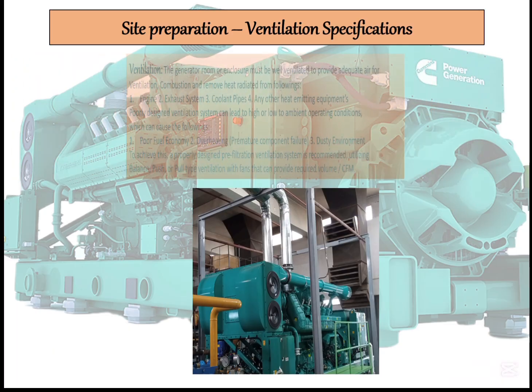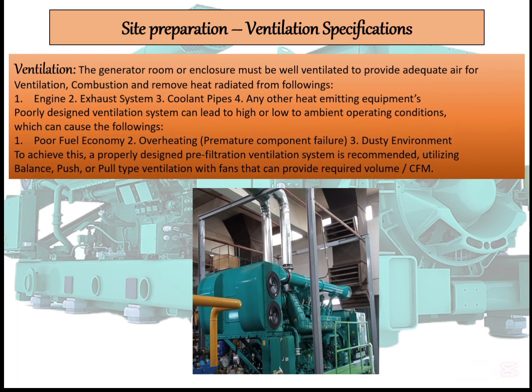The third part of site preparation is ventilation specifications. Gas engines are enclosed, with different settings inside the powerhouse or inside the enclosure. We need fresh air for combustion and cooling. A gas engine works with 80% air and just 20% gas. So we need to prepare a filtration system at the back to fetch fresh air from the surrounding atmosphere. That fresh air plays a crucial part in cooling and combustion. If our air is not clean, or if the temperature is hot, we have poor fuel efficiency and overheating problems. Dusty environments will impact the genset efficiency.